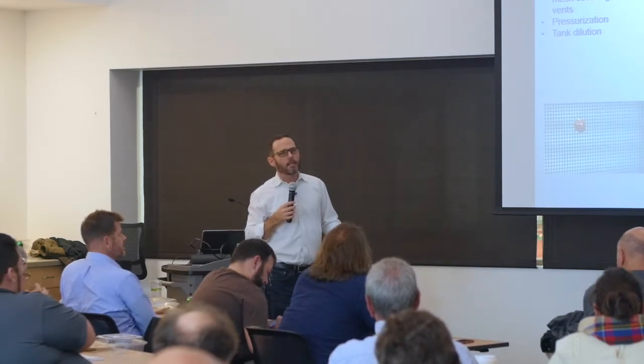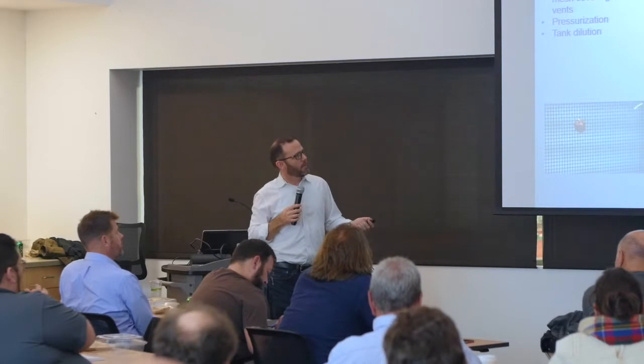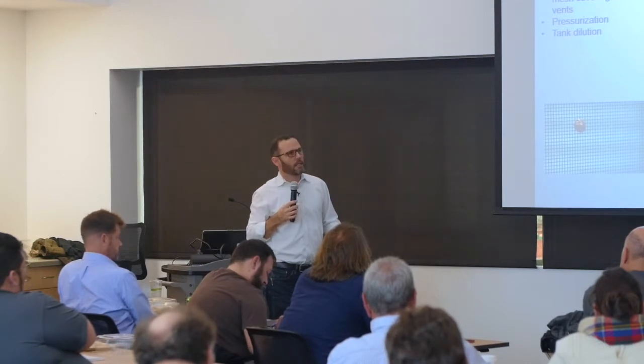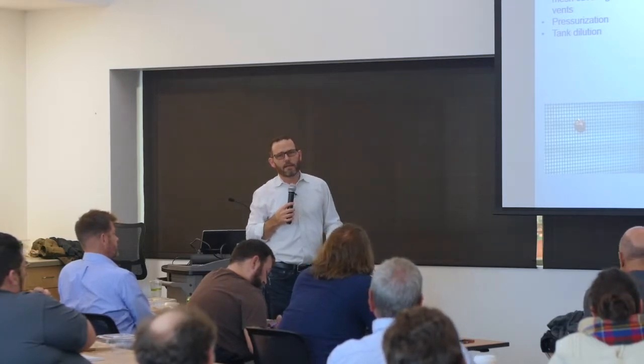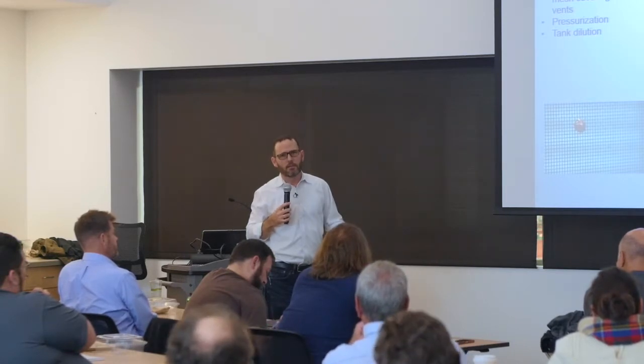Questions here? No. Keep it slightly positive, or what kind of pressure are you going for? Just because of how it was built, it ended up being slightly positive. It's also good to keep animal habitat slightly positive. You design it differently depending on what it is. This was actually engineered to be negative. It was never negative, just in order to get the airflows what they needed to be for ventilation, it ended up having to go positive. So this one was positive. The penguin enclosure is negative. That's mainly to keep the smell out of the guest area.